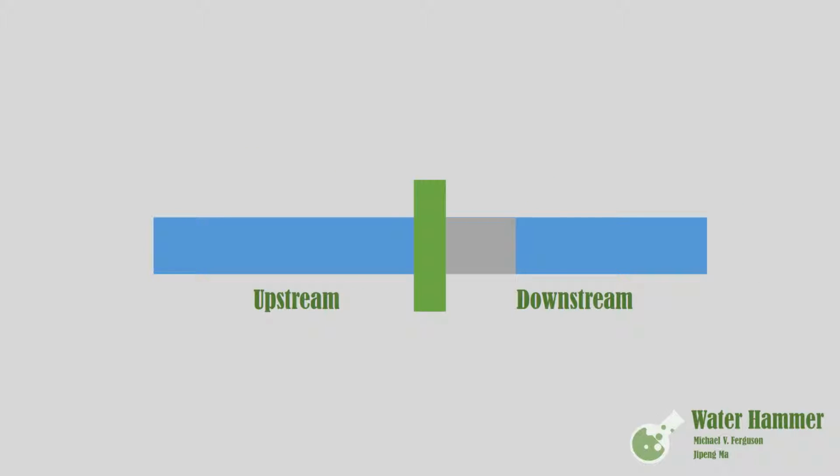In order to mitigate the effects of a water hammer, an arrestor can be placed upstream of the control valve. The arrestor is a piston full of air that will compress in the event of a water hammer, allowing water to rush into it to relieve pressure from the shock wave. Downstream, air relief valves can be implemented, which open the pipe to air in the event of a vacuum. This will equalize pressure inside and outside of the pipe to protect the pipe from damage.